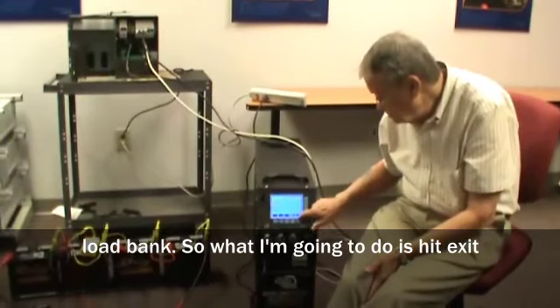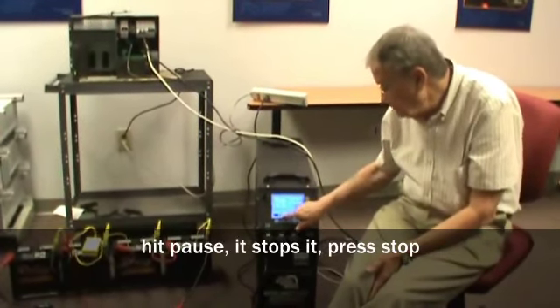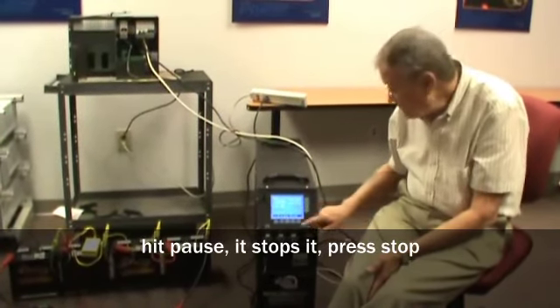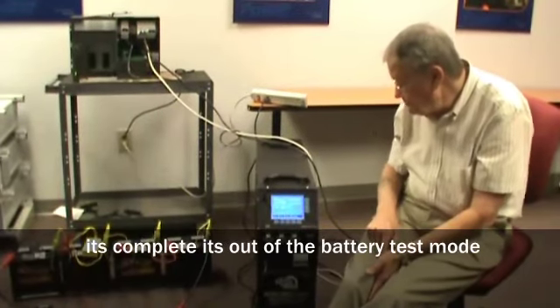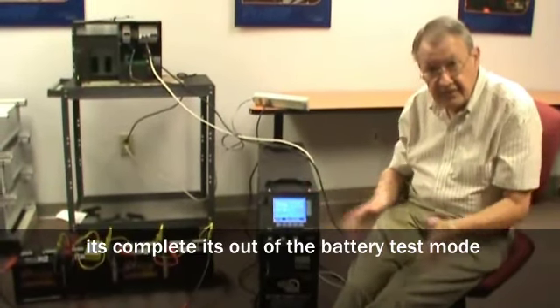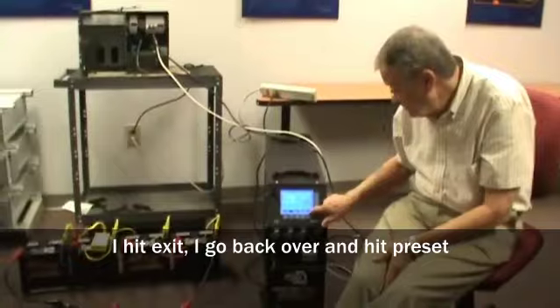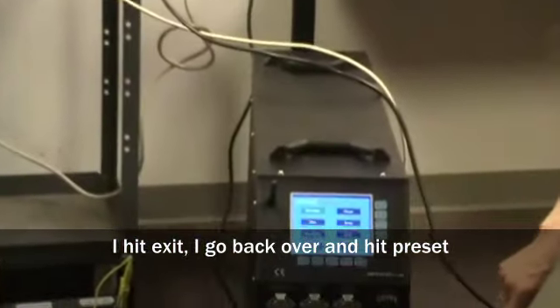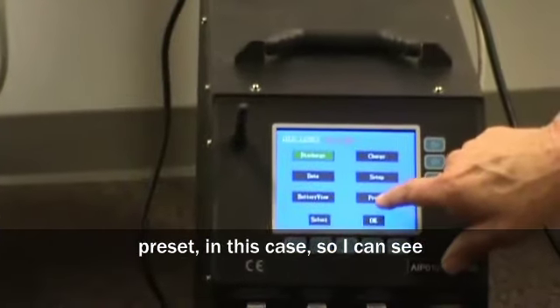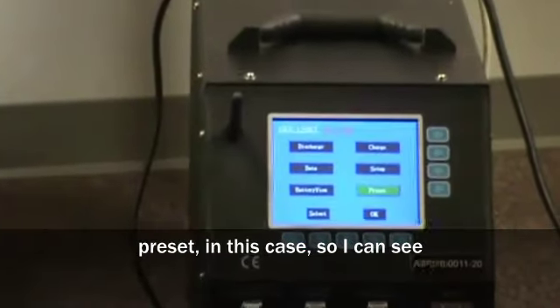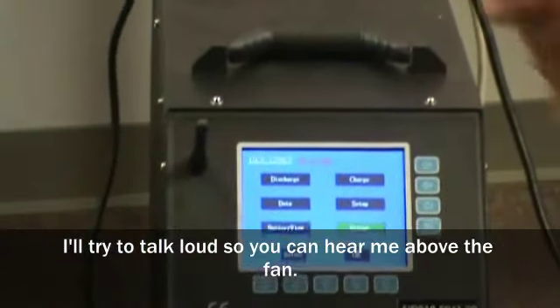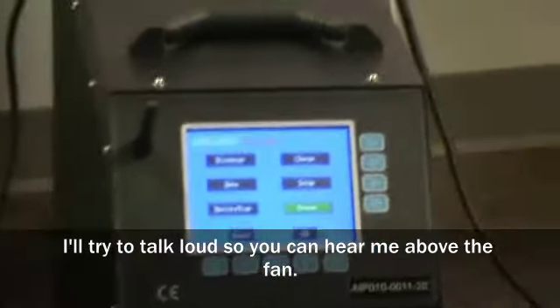So what I'm going to do is exit, hit pause, stop it, press stop, complete. It's out of the battery test mode now. I hit exit, I'll go back over and hit preset. And in this case, so I can see, and I'll try to talk loud so you can hear me above the fan, I'll go back to preset, I hit OK.